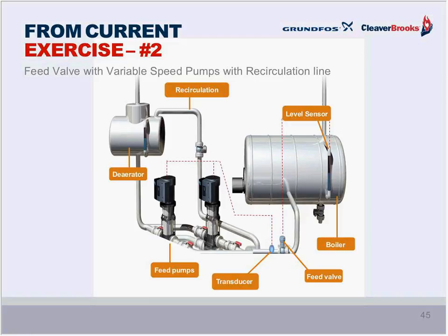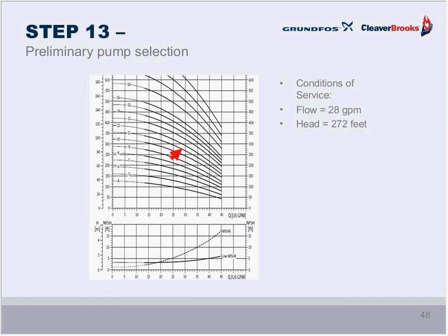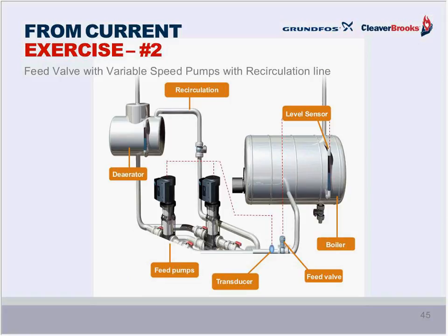Note that we've added a pressure transducer between the feed valve and the pumps. You can see the transducer there. As the level sensor in the boiler senses that raising and lowering of water level, it sends perhaps a 4 to 20 milliamp signal to the feed valve. That causes it to modulate more open or more closed, and that allows more or less water to flow from the pump to the boiler. The transducer senses that change in back pressure from the modulating feed valve, and it sends its 4 to 20 milliamp or some other signal to the controller for the variable speed drive, and that causes the pump and the motor to speed up or slow down to match the flow output to the actual steam demand and the water level in the boiler.